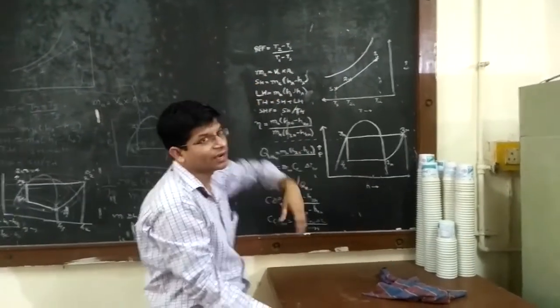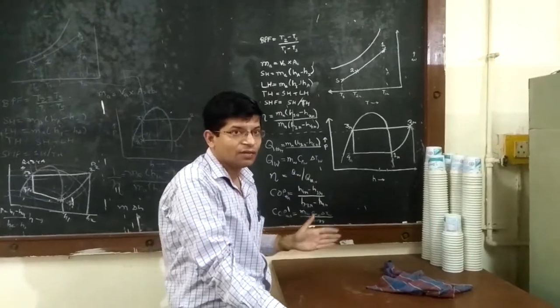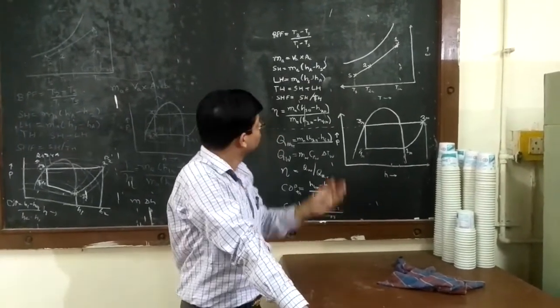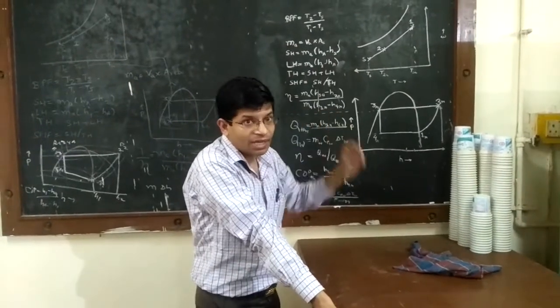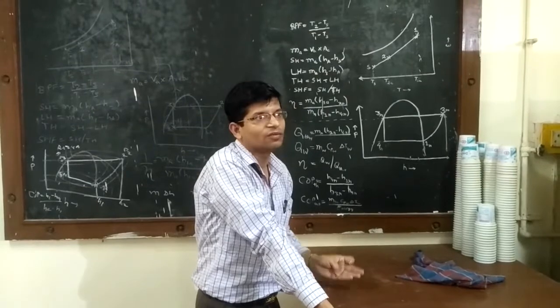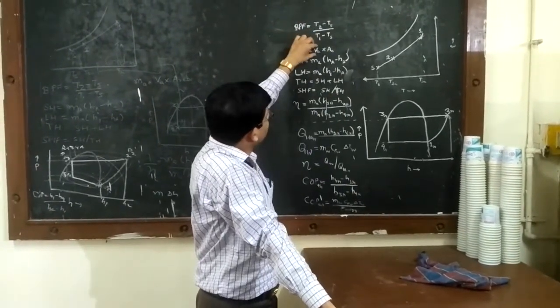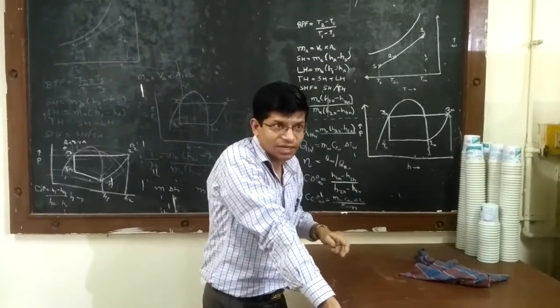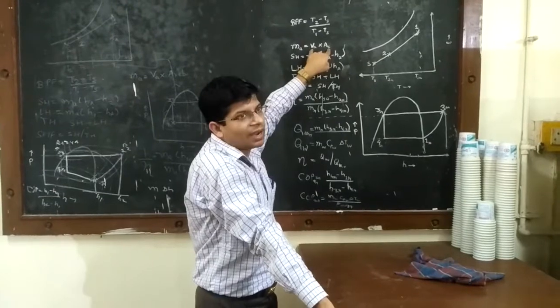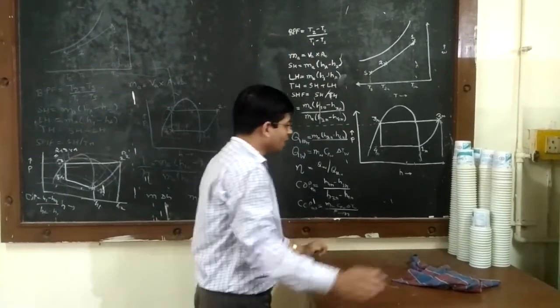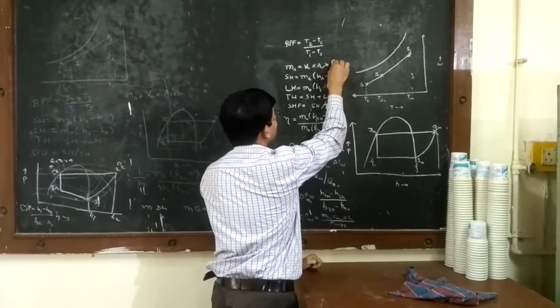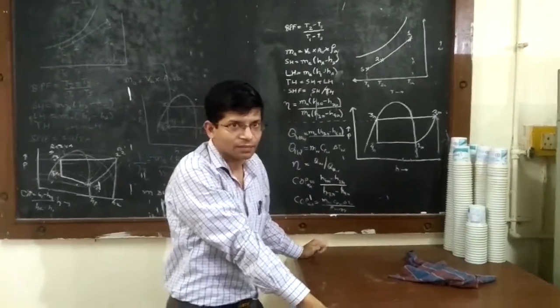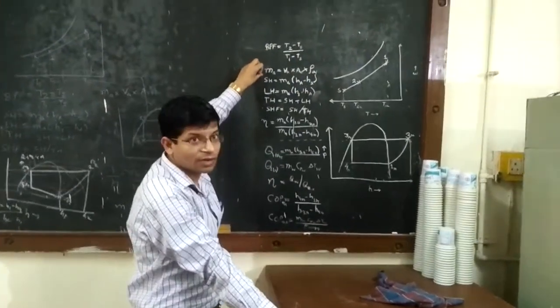Now, how to know the mass flow rate of air: for knowing the mass flow rate of air, we are required to use an anemometer. We have a unit of anemometer, so it will be measuring the air flow rate in terms of flow velocity in meters per second. Multiplying flow velocity by the cross-sectional area of the duct — which can be measured using a scale — we will be getting the volumetric flow rate, and then multiplying by density we get the mass flow rate of air.